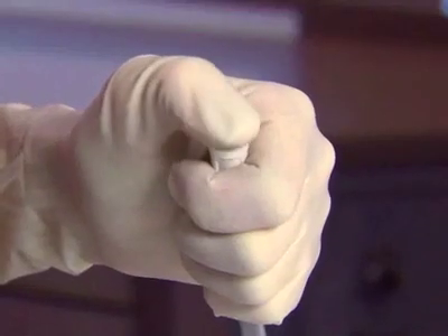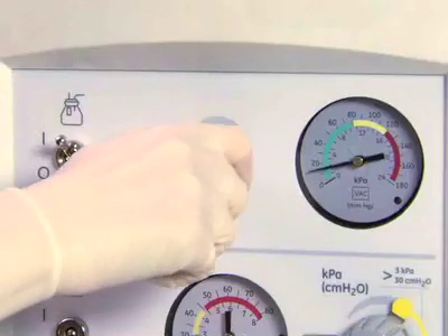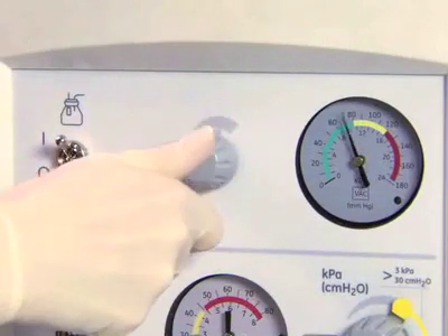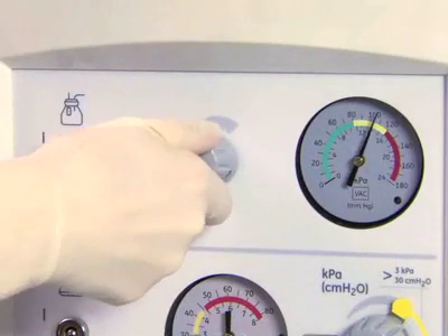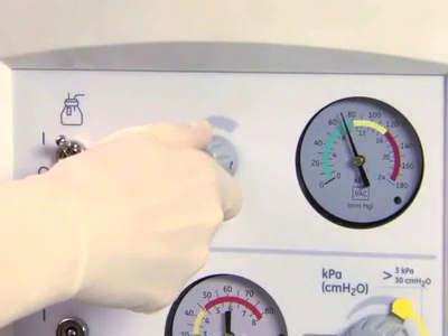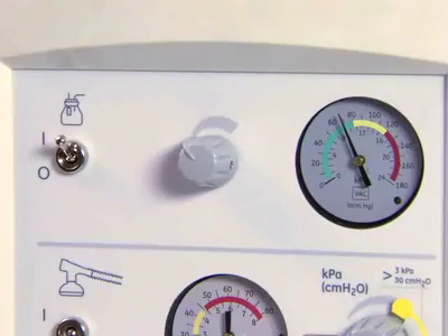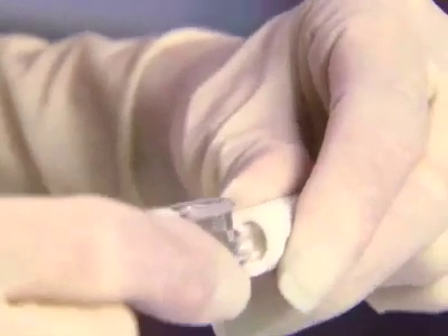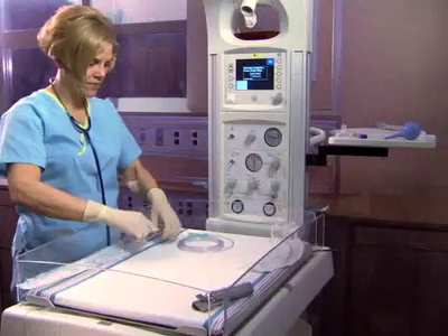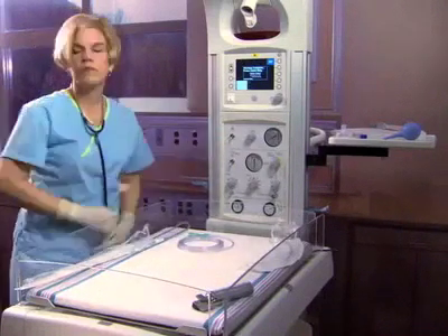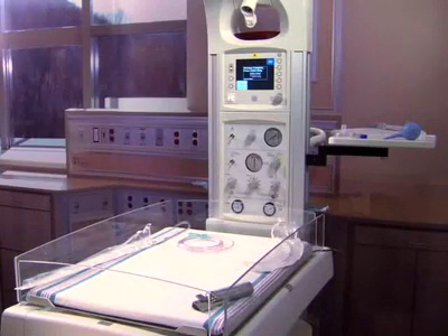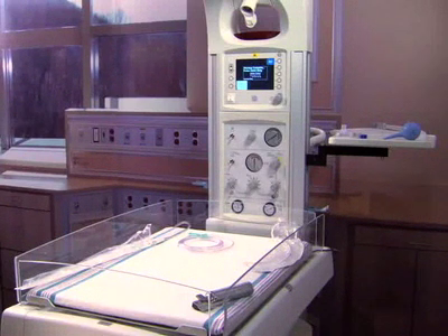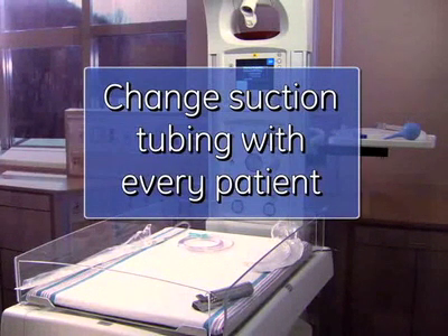Occlude the connective tubing, then adjust the suction control knob to a desired pressure between 60 to 120 millimeters of mercury. Once you have set the desired vacuum level, attach the suction catheter or meconium aspirator of your choice. Turn the suction control switch off until ready to initiate resuscitation or airway support measures to avoid wasting gas. Suction tubing between the canister and the patient should be changed with every patient.